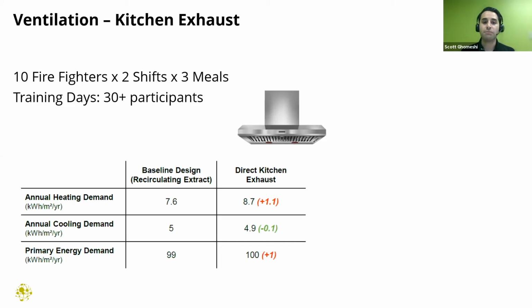That meant we had to find other ways of making up for that energy penalty. We found ways to balance the load, particularly on the ventilation side, such that the HRV serving that zone can remain a little unbalanced during extended cooking times. That's actually a positive effect, because when they're cooking over long periods generating a lot of heat and steam, running the HRV at a bit of an imbalance to bring in cooler air gives the firefighters relief - they actually prefer the space a bit cooler during cooking.